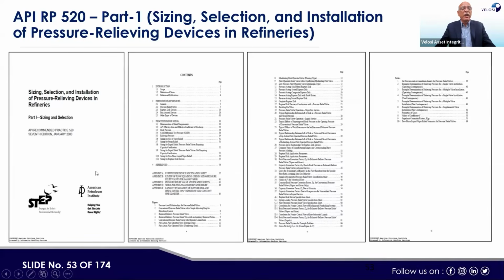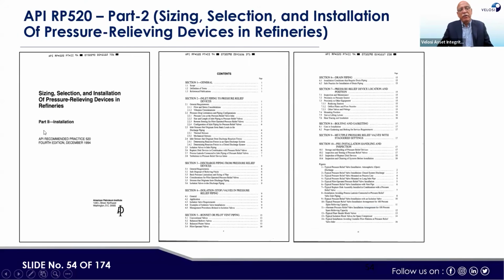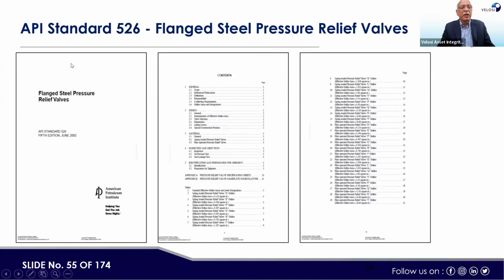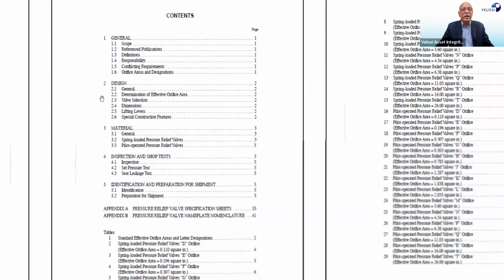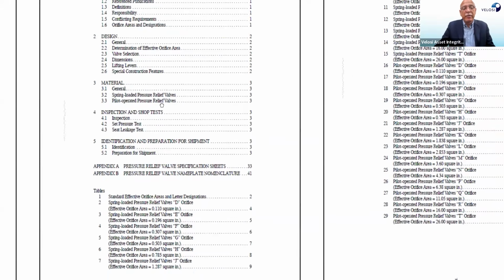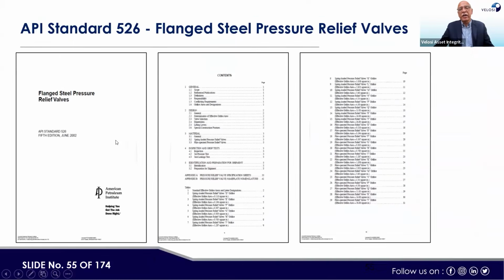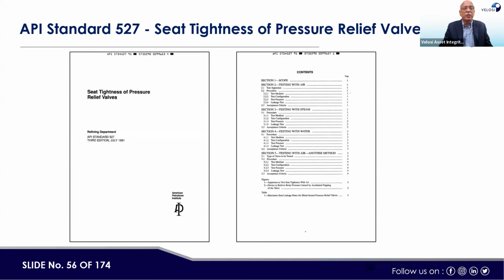If we go next, that is the API 520, sizing, selection, and installation of pressure relieving devices in refineries, sizing and selection part 1, and then installation part 2. So the API 520 has 2 parts. Then this is the standard specification for flanged steel pressure relief valves. If you see its contents, like general scope, design, then material, inspection and shop tests, then identification and preparation for shipment and other guidelines. So this is the standard which is used for the selection and sizing, for the purchase specification of the PSVs.